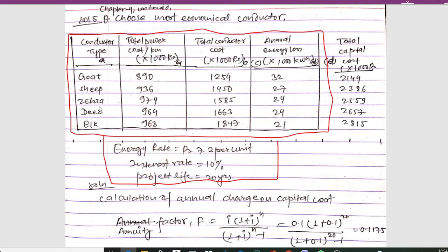The conductor types given are: Goat, Sheep, Zebra, Deer, and Elk. Similarly, the total power cost per kilometer is given in the table. We have also been given the total conductor cost, and in the next column we have the respective values for annual energy loss for each conductor.